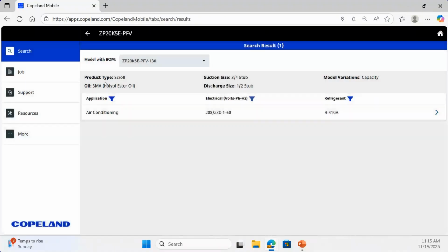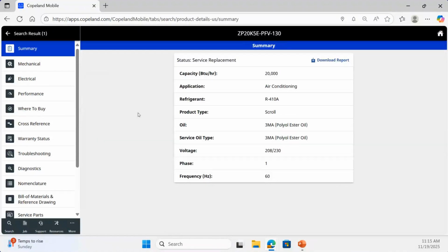I can see here that that compressor is only rated for 410A, so that's what I'll choose in the application. What we're going to do out here is figure out what's going on with this compressor. I'm going to turn it over to James here to get into the troubleshooting portion.